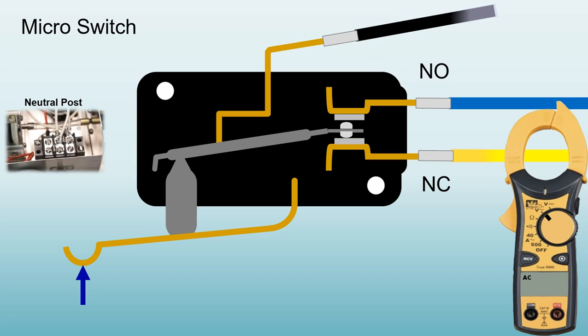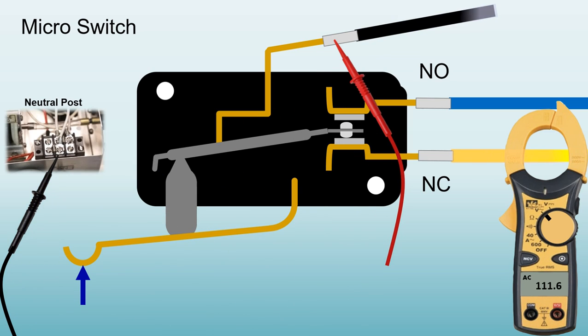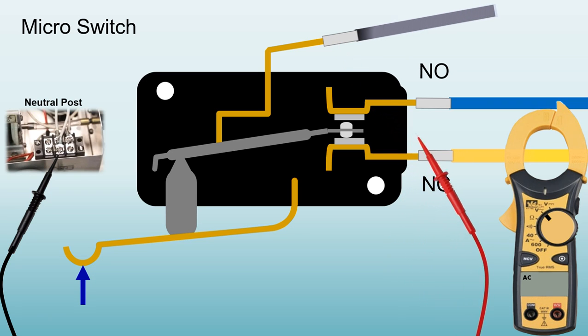Let's take a look at a micro switch. Micro switches are very common in our line of work. To be able to test a micro switch while it's connected to voltage, we put one of our meter leads on the intake side of the power and one on a common, again using a neutral post or any white wire that you find in the system will complete the circuit. On a micro switch, you have a normally open and a normally closed circuit. So while it's in its resting position, we can move our meter lead to the normally closed circuit to verify that we have power coming out.